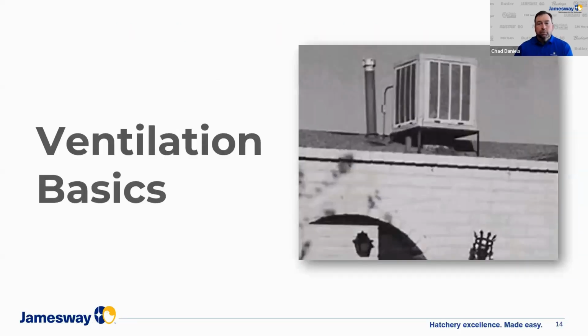So in the beginning, when we look at a lot of the original ventilation systems that were applied to hatcheries, this picture illustrates just a common roof-mounted evaporative cooler. It's basically a blower that pulls fresh air across a wetted cardboard evaporative cooler pad. And by doing this, the air entering is slightly cooled and humidity is added to that. And then that air is basically just dumped or supplied directly into the room.